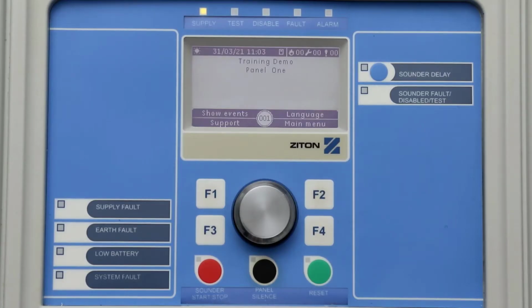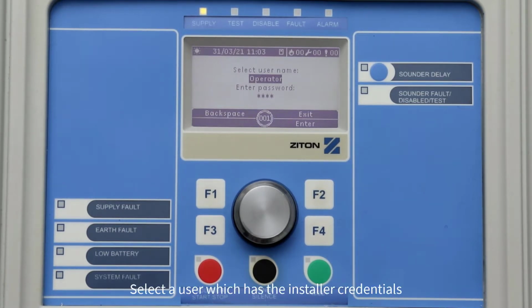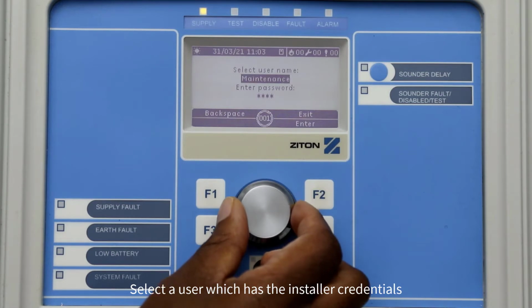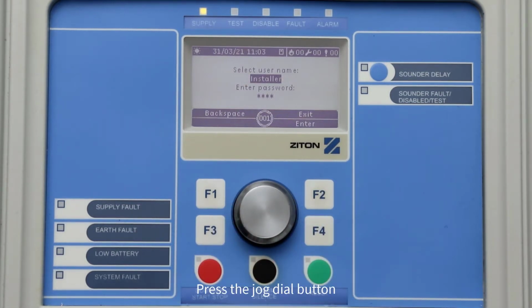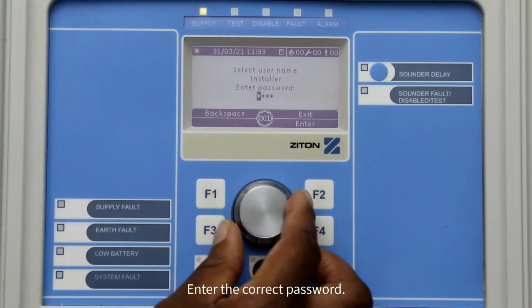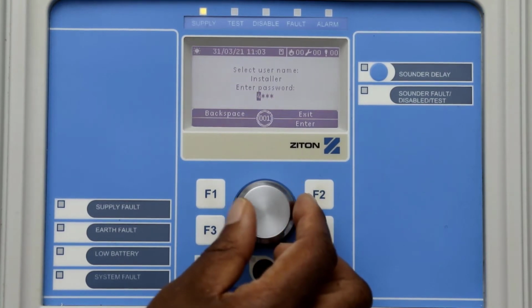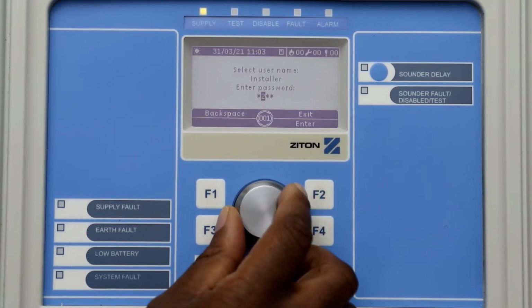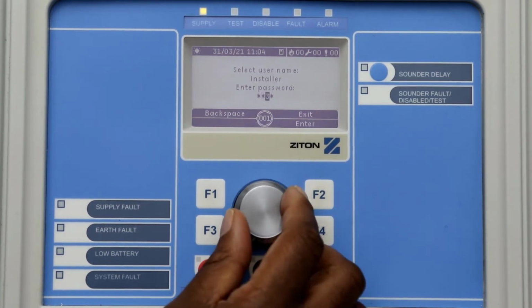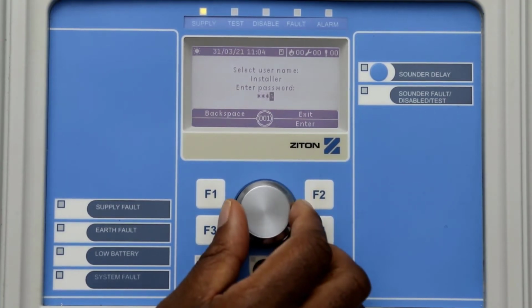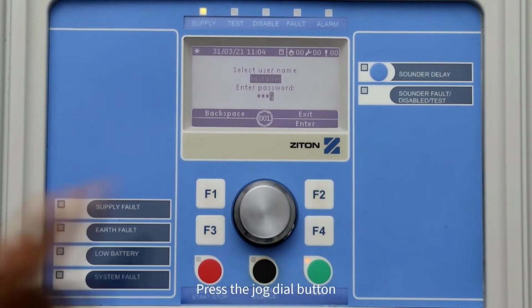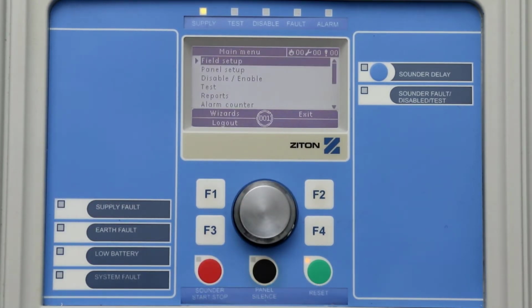To log into the panel as an installer, press F4 to select the main menu. Using the jog dial button, turn the dial and select a user which has the installer credentials. Now press the jog dial button to scroll down to the password option. Using the jog dial button, select the correct password for the user. To do this, simply turn the jog dial button to select the correct number, and pressing the jog dial button will move the cursor to the next digit. Now press the jog dial button or F4 to enter into the installer menu.